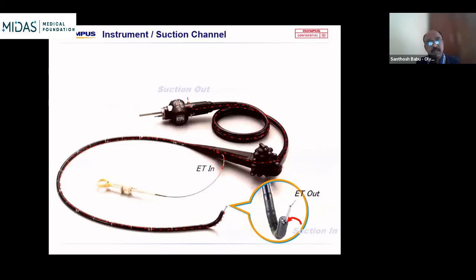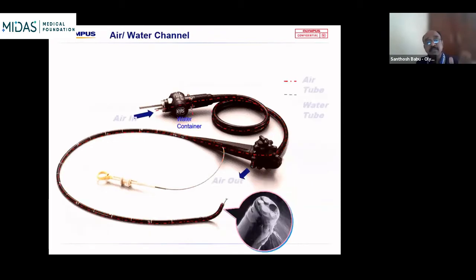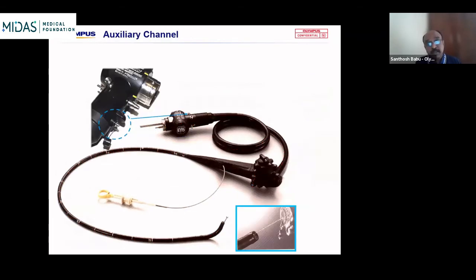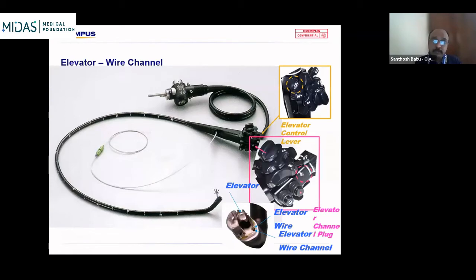Now going on to the channels of the endoscope, it's just like your regular scope channels. Definitely it has a suction channel, which also works as an instrument channel. Then you have the air water channel, an air channel feeding in air or CO2 for inflating or to remove the water content on the objective lens. Then you have the water auxiliary channel. Yes, we do have these auxiliary channels in the regular endoscopes for cleaning the mucosa. We do have such a channel in the ultrasound endoscope, especially the forward-viewing ultrasound endoscope. The elevator channel is also available. You have the elevator channel for the linear scope to orient the instrument. Yes, these are the open type elevator channels, which are common in the ultrasound endoscopes.